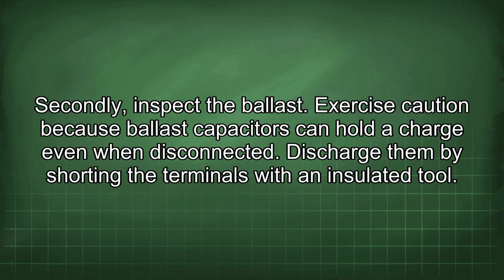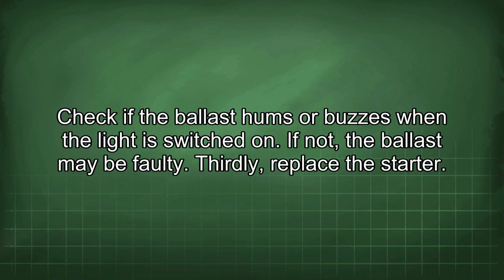Secondly, inspect the ballast. Exercise caution because ballast capacitors can hold a charge even when disconnected. Discharge them by shorting the terminals with an insulated tool. Check if the ballast hums or buzzes when the light is switched on. If not, the ballast may be faulty.